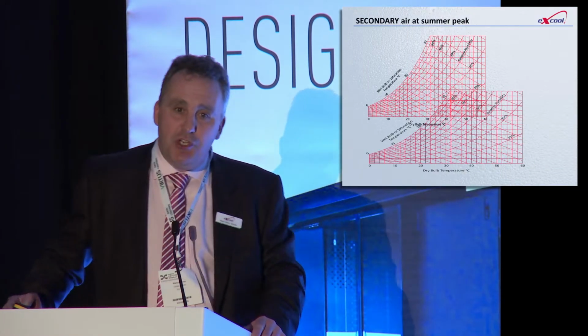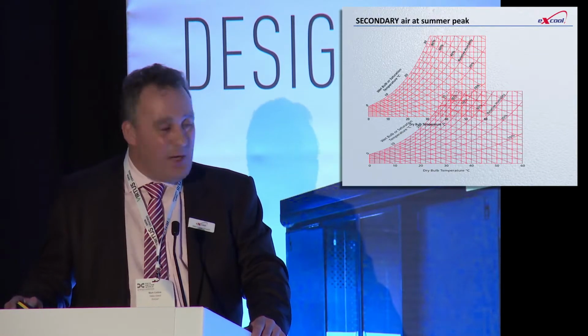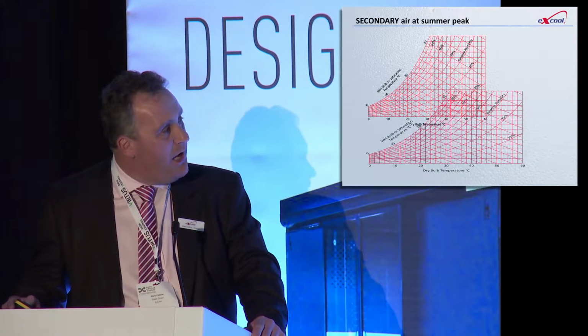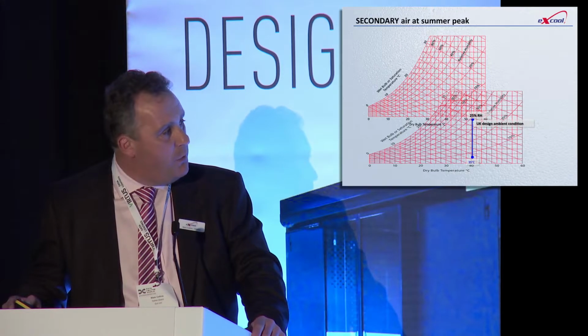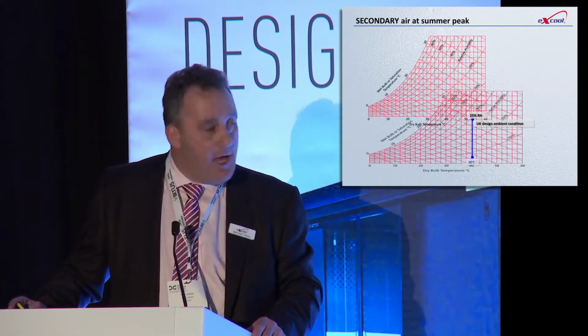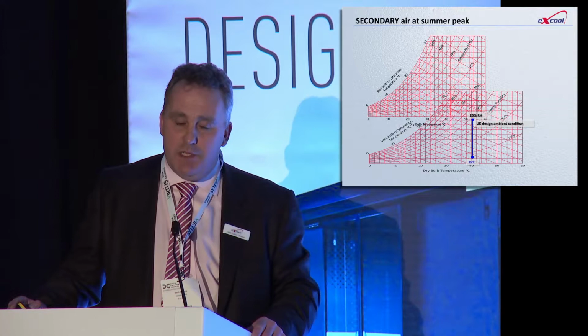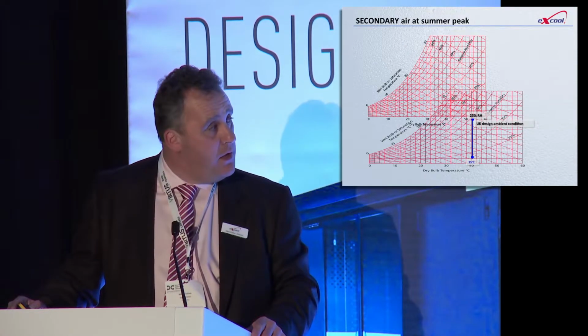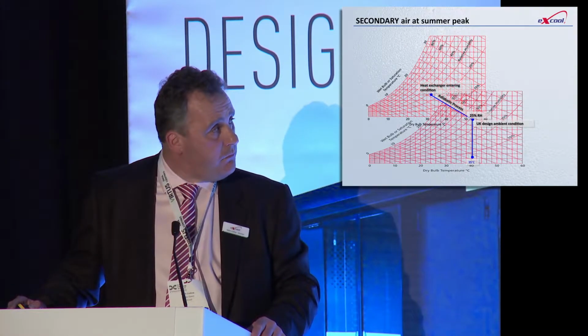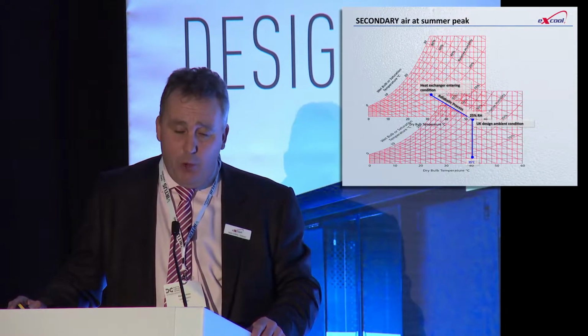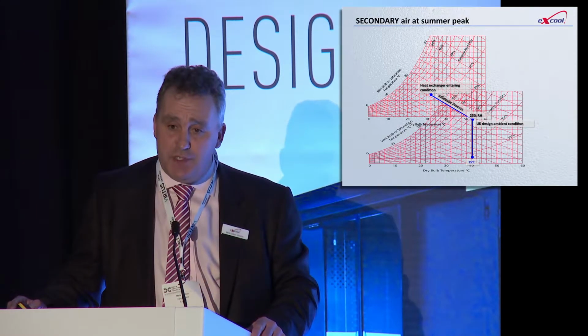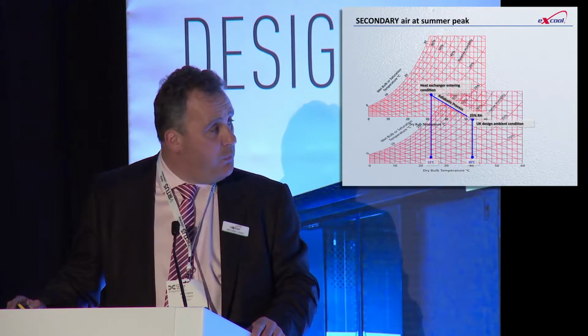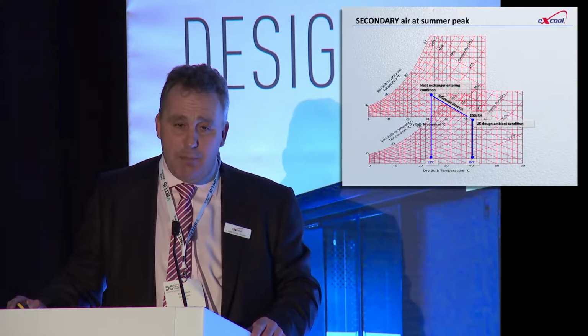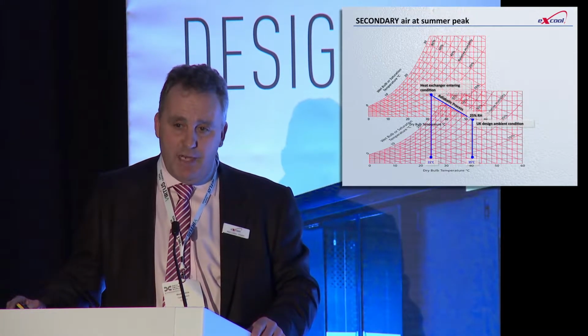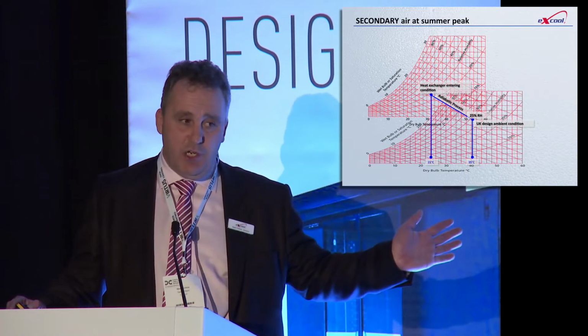The dreaded psychrometric chart, but I need this just to describe to you exactly what's going on. Typically in the UK, we would be here. We would be at 35 degrees C and around 25% relative humidity on a peak summer day. To that we add moisture. By adding moisture, that takes us up the wet bulb line, increasing the humidity to 100%. We effectively now have lowered the outdoor air temperature from 35 degrees C to 21 degrees C simply by adding moisture. And it's this that we use as a cooling medium.